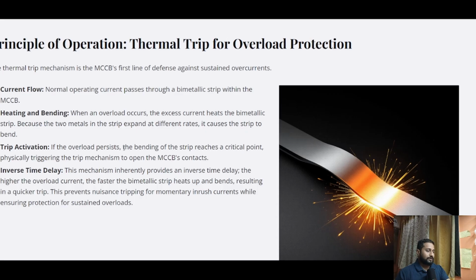If the overload persists, the bending of the strip reaches a critical point, physically triggering the trip mechanism to open the MCCB's contact. And it also has inverse time delay. This mechanism inherently provides an inverse time delay. The higher the overload current, the faster the bimetallic strip heats up and bends, resulting in a quicker trip. This prevents nuisance tripping for momentary inrush currents while ensuring protection for sustained overload.